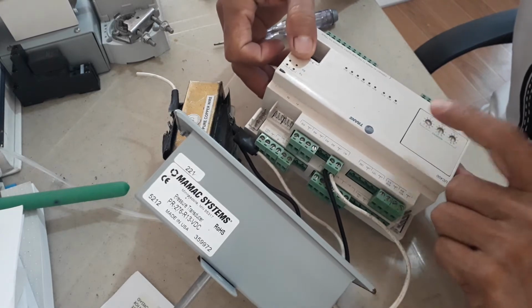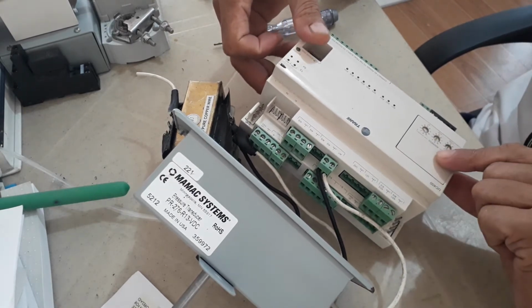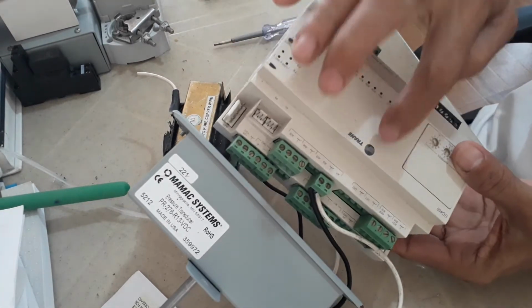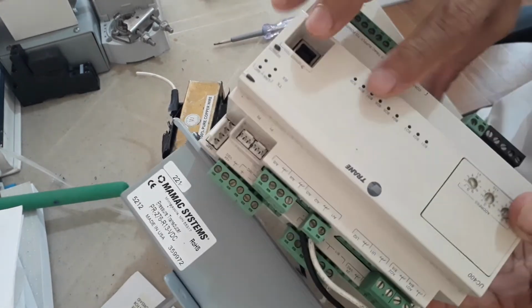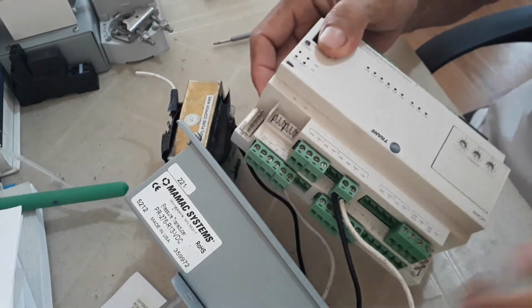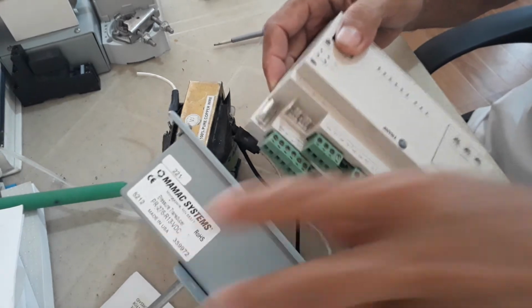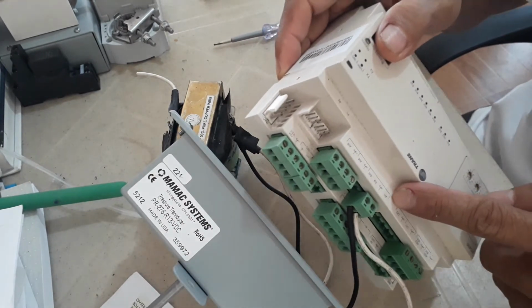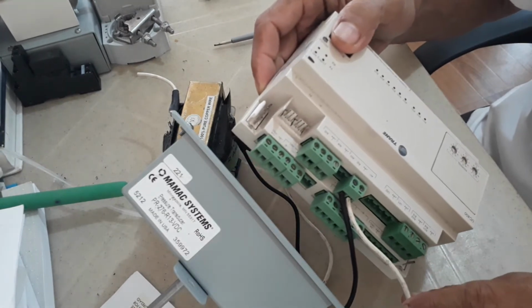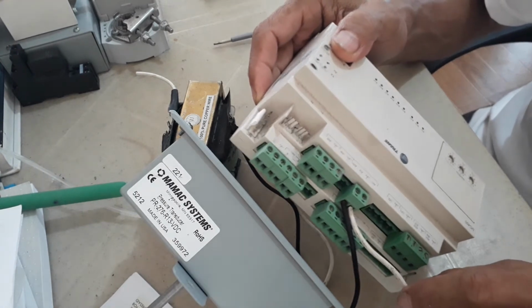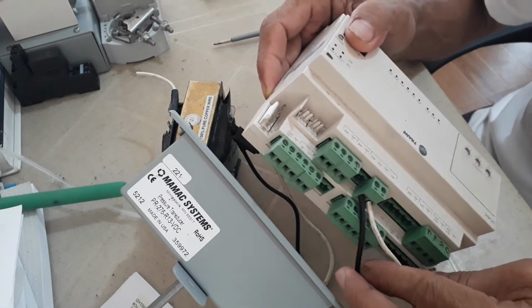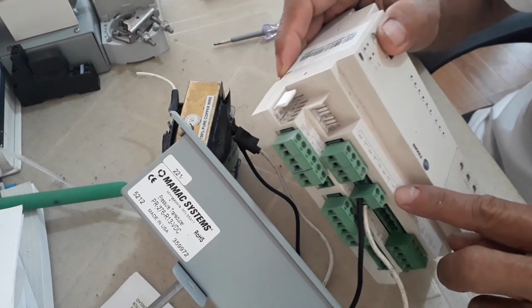Okay. Now I have here a DDC. This is a Trane. As you can see here, this is Trane UC400, okay? So I'm wiring the output to one of the analog inputs, A1. So white is the 0 to 10 volts, then this is the common, okay? So analog input number 1.